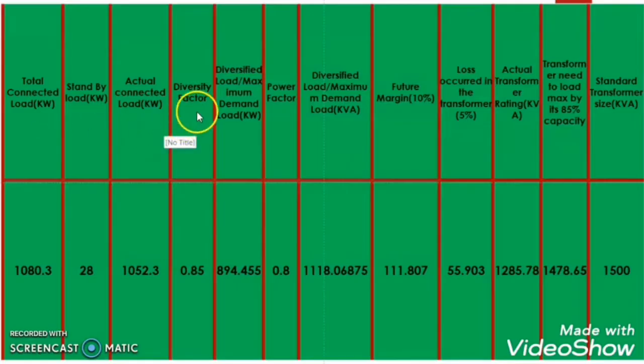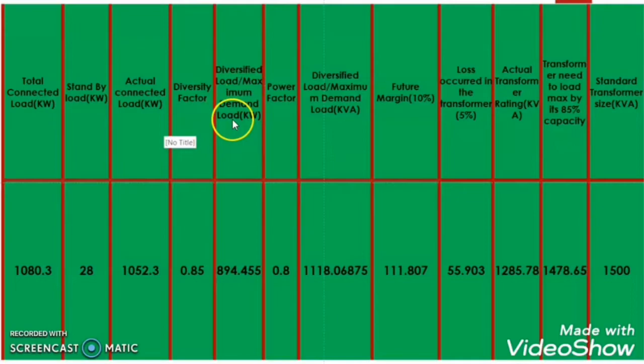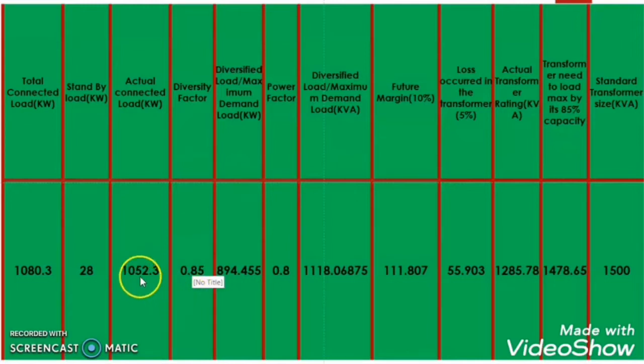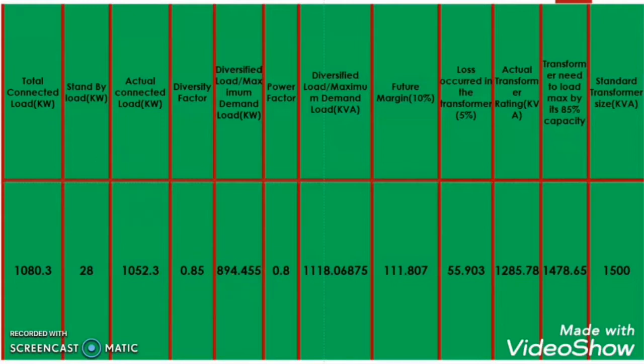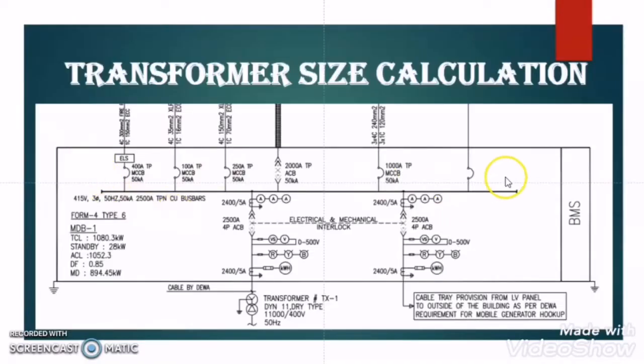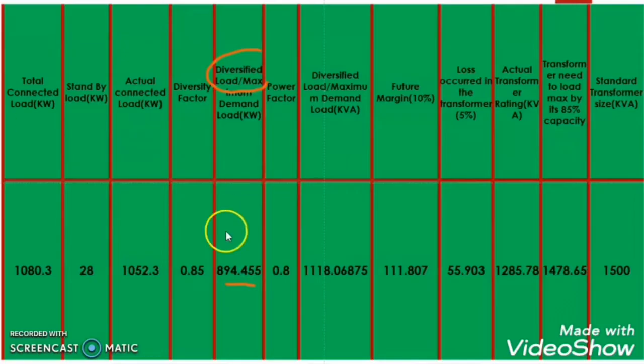The diversity factor is 0.85. So the maximum load, or the load which is running on this LV panel, will be actual connected load multiplied by the diversity factor. The diversity factor is 0.85, so the diversified load or the maximum load on this LV panel at a time is equal to diversity factor into actual connected load. So it will be 1052.3 into 0.85, which comes to 894.455 kW. This is the diversified load or the maximum load which will occur on this panel at a time.